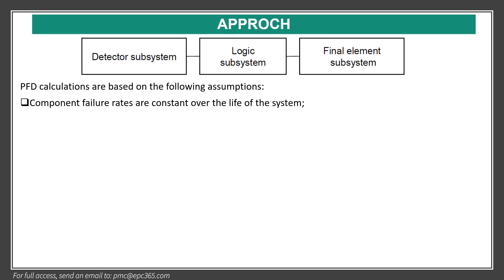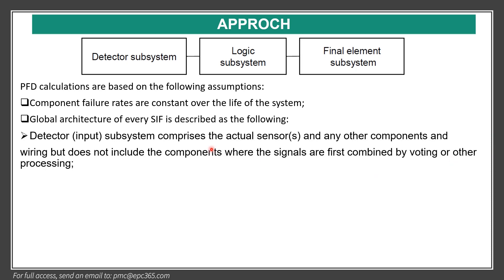Here I explain the approach. We have a detector subsystem, a logic subsystem, and a final element subsystem. The probability of failure on demand is based on the following assumptions: component failure rates are constant over the life of the system. The global structure of the SIF is described as follows: the detector input subsystem comprises the actual sensor or any other components and wiring, but does not include the component where signals are first combined by voting or other processing.